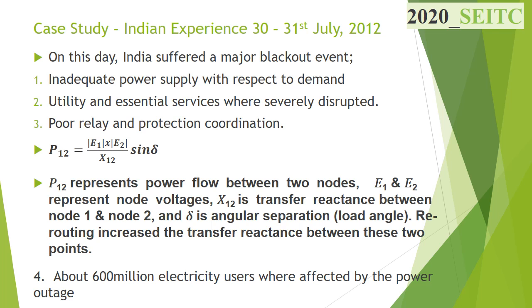The network interconnections between the northern region and western region of Uttar Pradesh were out of supply due to scheduled and forced outages at the time of the disturbance. The only remaining link between the northern region and western region is the 400 kV Bina-Gwalior-Agra line, which became overloaded. The Regional Load Dispatch Center initiated load shedding and directed the Western Region to reduce generation to curb the power flow, but the response was not quite enough. It didn't come at the time it was expected.